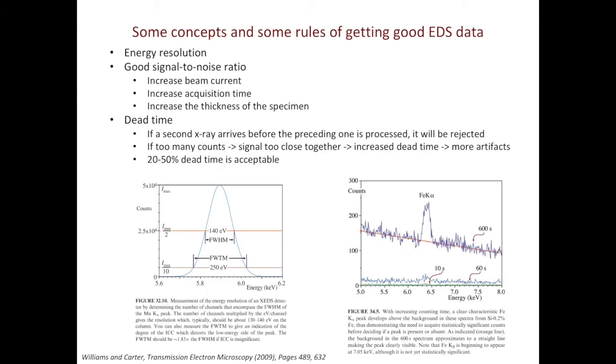Let's also look at some concepts and some rules of getting good EDS data. In TEM, we talk about spatial resolution. In spectroscopy, we talk about energy resolution. The energy resolution is usually defined as the full width half maximum. For a regular EDS, the full width half maximum for manganese K-alpha is about 140 eV. We will come back to this when we discuss electron energy loss spectroscopy, EELS.